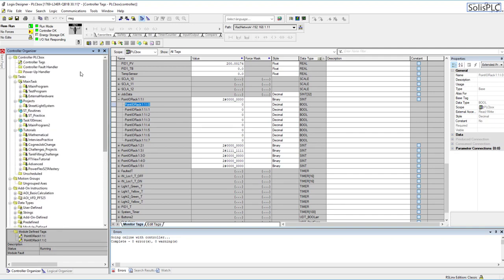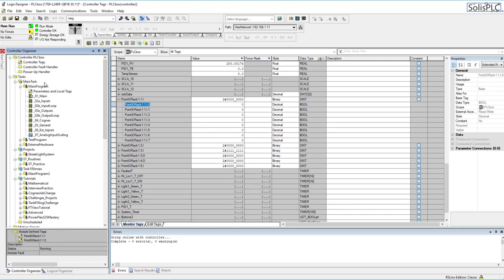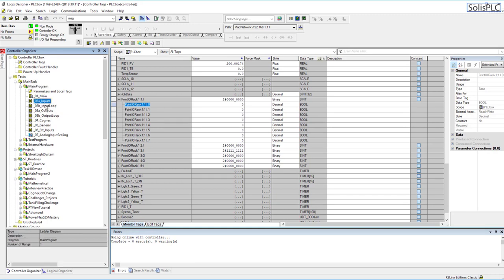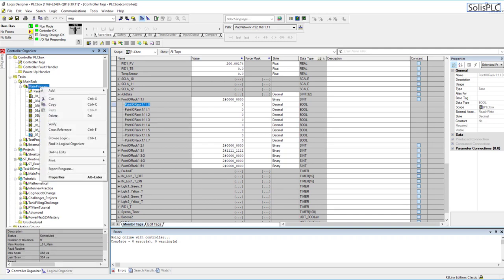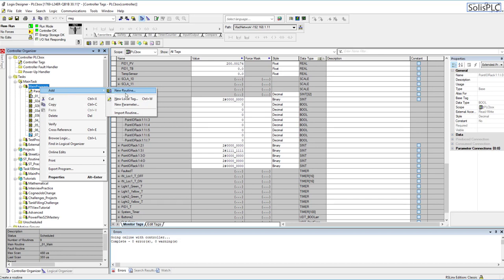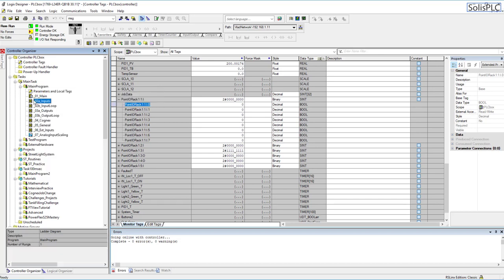Here we're going to start with slot number one which is a digital input card. The way I usually set up my tags is I go back to the main program and then I go into the input section. This has already been pre-created on the PLC. In case you need to add this you need to right click main program, create add and then a new routine. We're going to do it in ladder logic just to simplify the process.